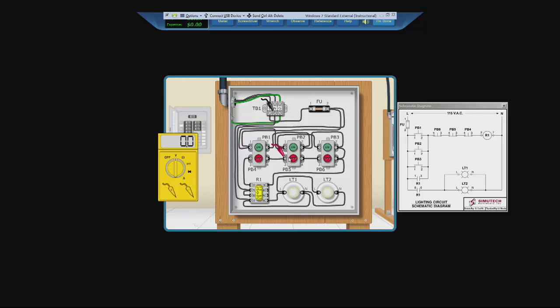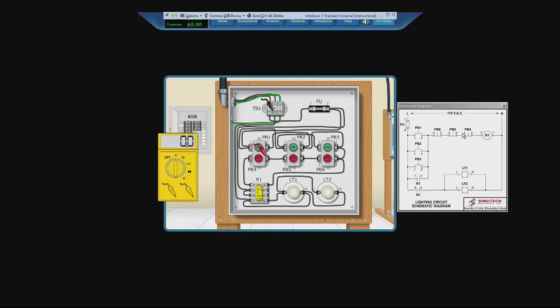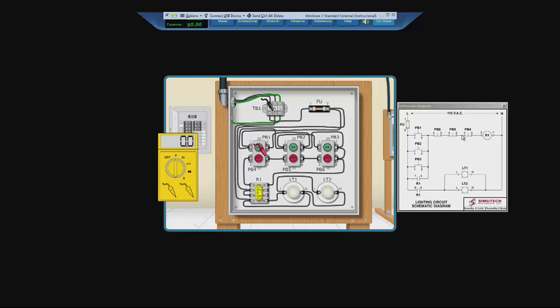So let us go to PB5. Test it. So let us go to PB4, this is in between the two points we have just checked. If we get power here, it means it's this switch that's wrong, it's shorted open. But if we don't get power here, it means this wire is open. Let us test it. No power. So we know what is wrong.